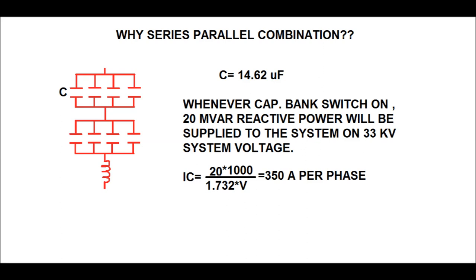Why is the series-parallel combination used instead of a single unit? The value of each capacitor unit is C = 14.62 microfarad. Instead of a series-parallel group, we could use a single unit in each star connection with value 2C, that is approximately 29.24 microfarad.